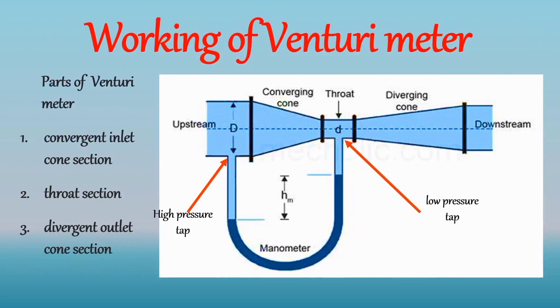Now Venturi tube is most preferred for flow measurement of slurries and liquid containing solid, provided the pressure tap is protected from plugging. Well since the flow area smoothly changes, the pressure recovery of Venturi is better than orifice.